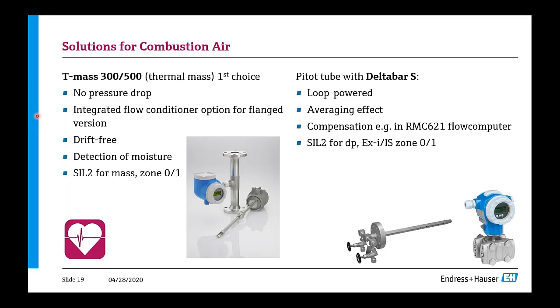But the problem with the T-mass is, okay, you wouldn't have any issues with dirt sitting on it because the combustion is relatively clean. However, because you have a relatively large duct, it's hard to find a good point. And the temperature limitation is now 180 degrees C. I'm not sure if that's sufficient. Typically, I think you should be lower if you have enough energy taken out through the heat recovery. The other one, the Pitot tube, from a pure economic standpoint, is cheaper.